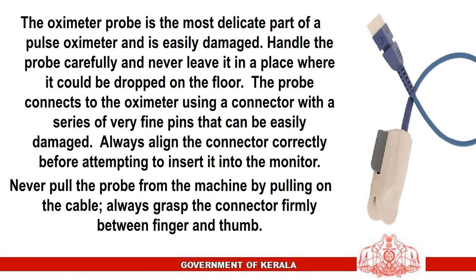The oximeter probe is the most delicate part of a pulse oximeter and is easily damaged. Handle the probe carefully and never leave it where it could be dropped on the floor. The probe connects to the oximeter using a connector with very fine pins that can be easily damaged — always align the connector correctly before inserting it into the monitor. Never pull the probe from the machine by pulling on the cable; always grasp the connector firmly between finger and thumb.